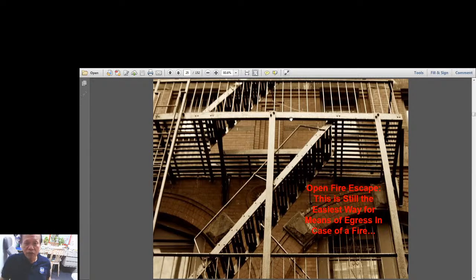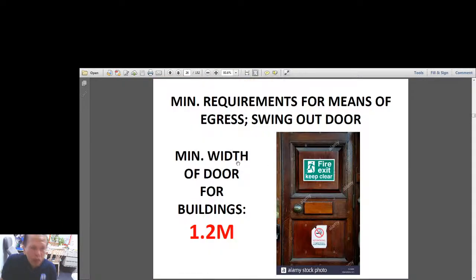So that's why the Bureau of Fire people will always require a fire exit, because the moment you come out of your window and go to here, you are already exposed to fresh air. So even if the smoke is coming your way, at least it will not be as devastating as when you are inside an enclosed stairwell and the smoke is so bad. Oh, very dangerous. So you have to check on this when you inspect the minimum width of doors for exits. 1.2 meters should be the minimum width of fire exits, and they must be provided with exit signs very clearly, so that people would know where to run for safety.